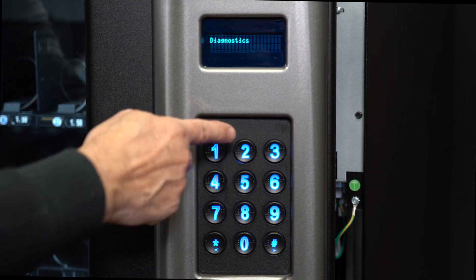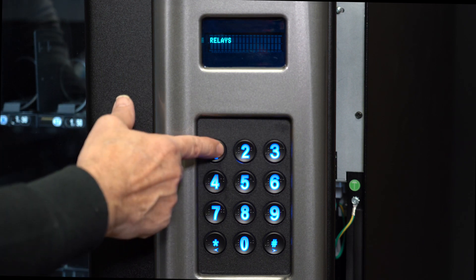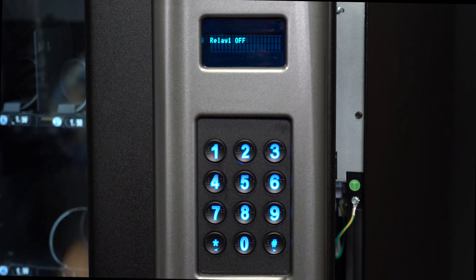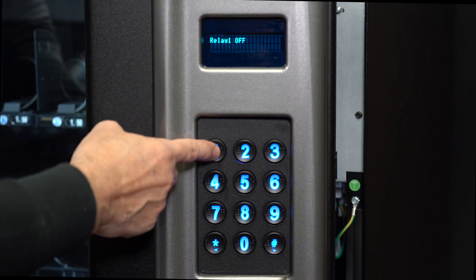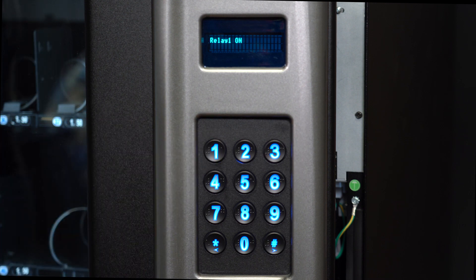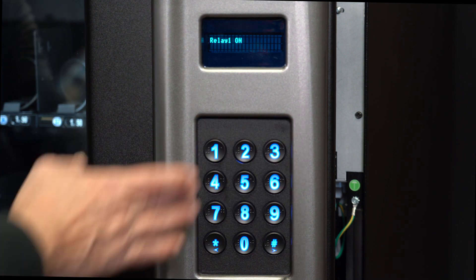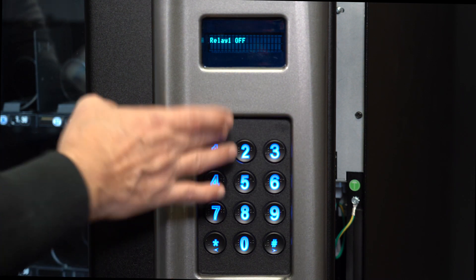Pressing 2 gets you to the relays menu. Press 1 to go to relay 1. If relay 1 is off, press 1 again to turn it on to force the compressor and fan to turn on. Press 1 to turn it off.